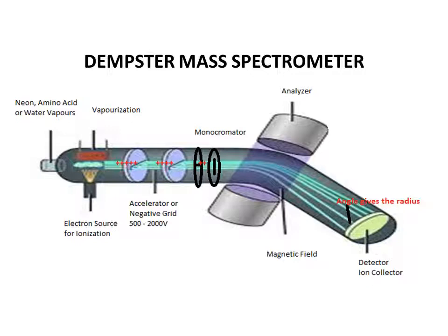After the monochromator, it will move towards the analyzer for analysis. And after the analyzer, the ions will make a curve and fall upon the detector. From the detector, it will move towards the amplifier, and from the amplifier, it will give peaks on the computer.